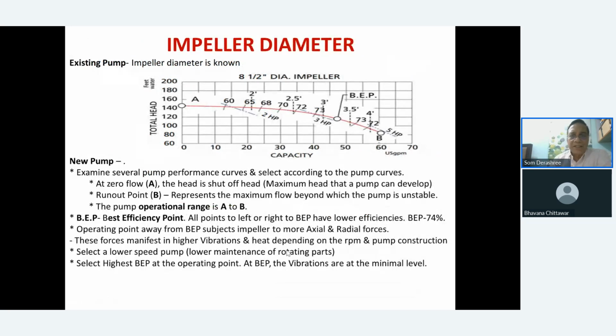Again, on impeller diameter, you would find from these curves, if there is an existing pump, of course, you already know, but for a new pump you have to examine several pump performance curves and select according to them. At zero flow, that is this point A, it's the shut-off head. That's the maximum head that the pump can develop. Of course, you can run it, but the water will be churning, and at one point, with the heat, it will convert into steam, and then there will be a lot of leakages and problems in the pump.